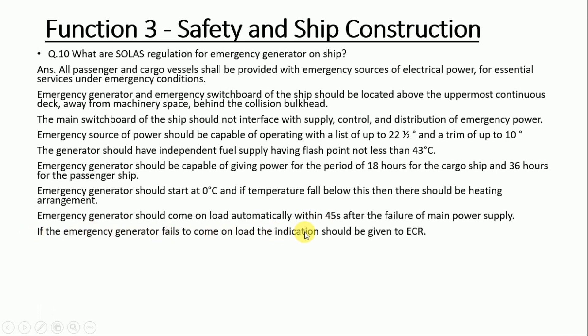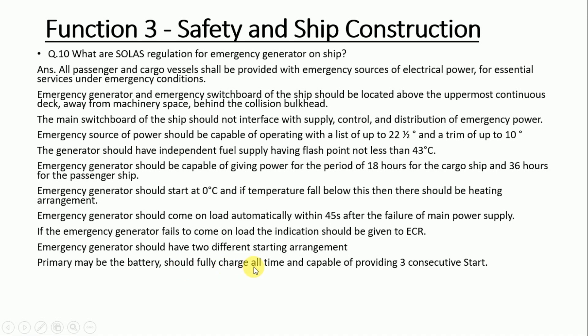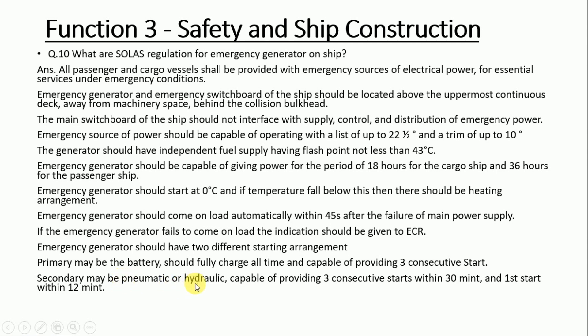If the generator fails to come on load, an indication should be given in the engine control room. The emergency generator should have two different starting arrangements — for example, battery start and hydraulic start. The primary battery shall be fully charged at all times and capable of providing three consecutive starts. The secondary system, either pneumatic or hydraulic, shall be capable of providing three consecutive starts within 30 minutes, with the first start within 12 minutes.